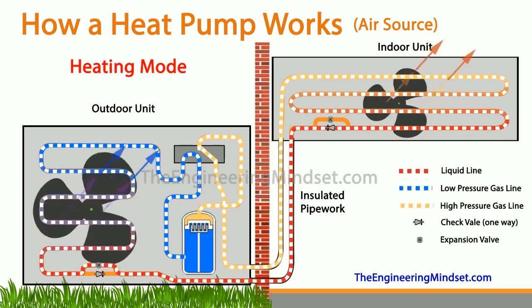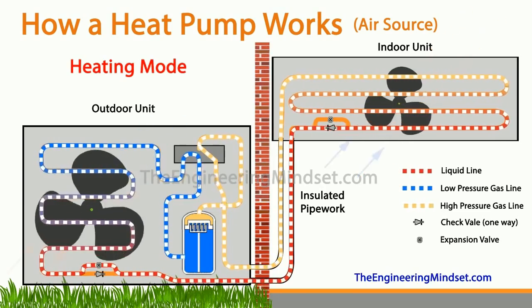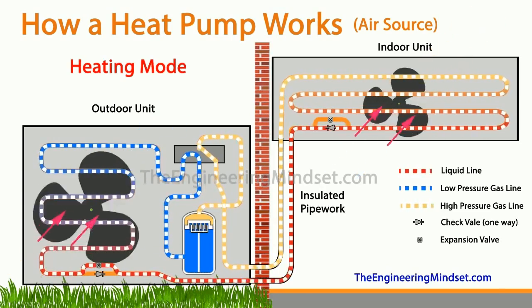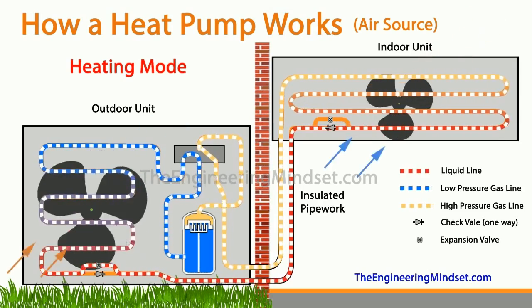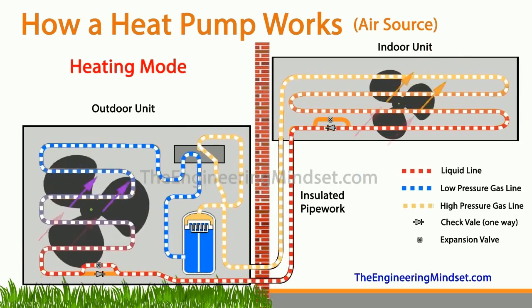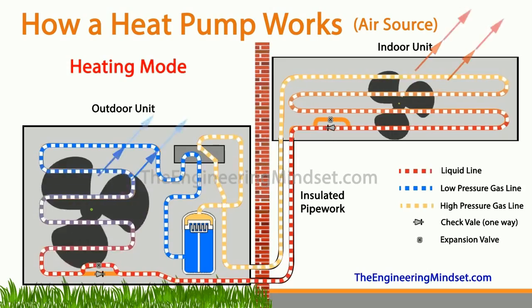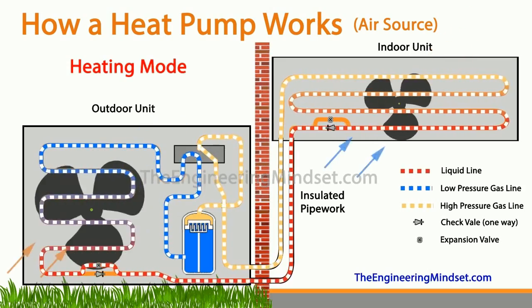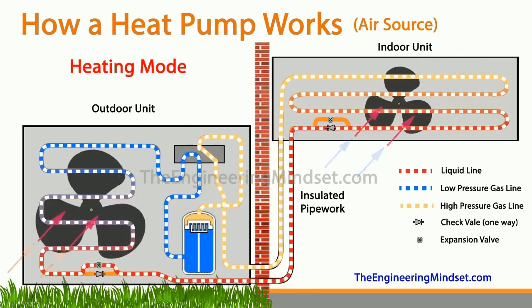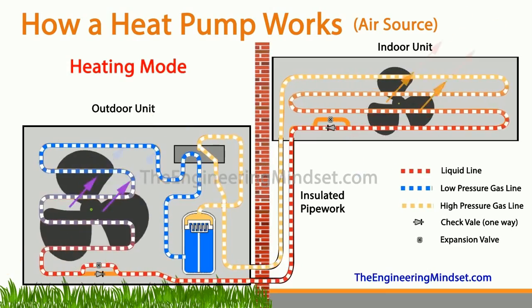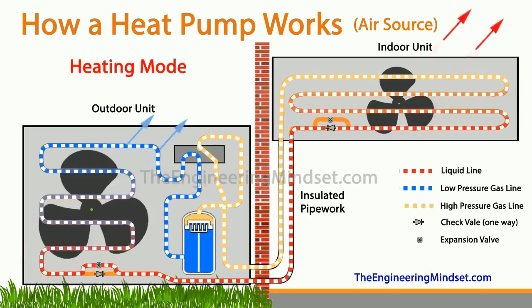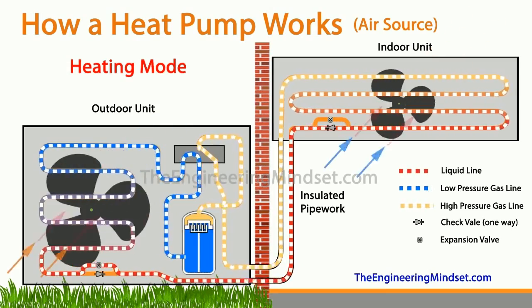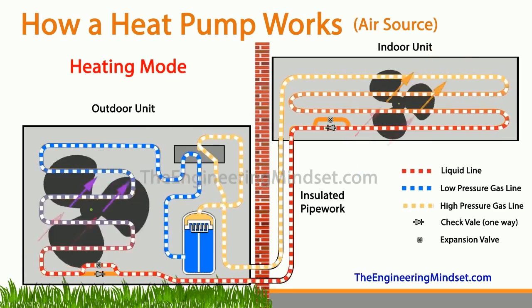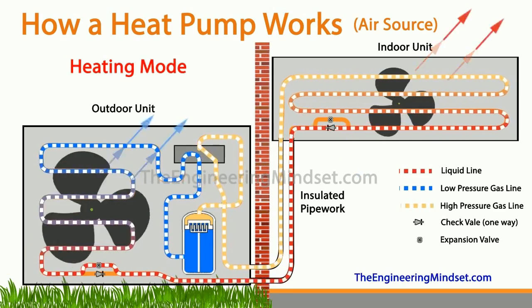Now a lot of people say, well, what about in the winter time? The air is cold, there's no energy in there, how do you take energy from the air then? Well, actually that air still has a lot of energy in there, and certainly enough to be extracted by a heat pump. As long as the air is above minus 273 degrees Celsius, then there is energy in that air which can be extracted, and obviously we're not going to be going down to that temperature in our climates.